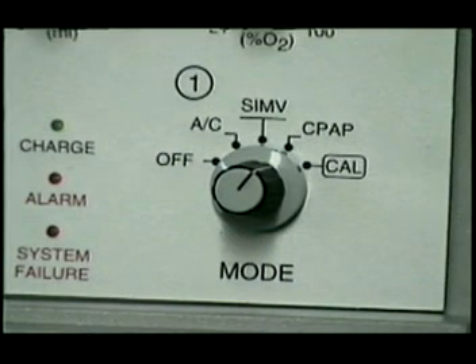In the CPAP mode, the patient does all of the work of breathing, all of the time, and is subject only to the set air-oxygen mix and PEEP. If the patient does not breathe within 10 seconds, 6 breaths per minute rate, in the CPAP mode, an apnea alarm and operating backup mode are activated. The patient starts receiving controlled ventilations at a rate of 12 breaths per minute.